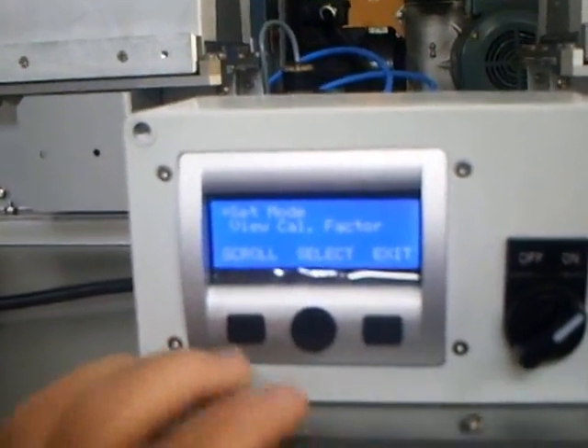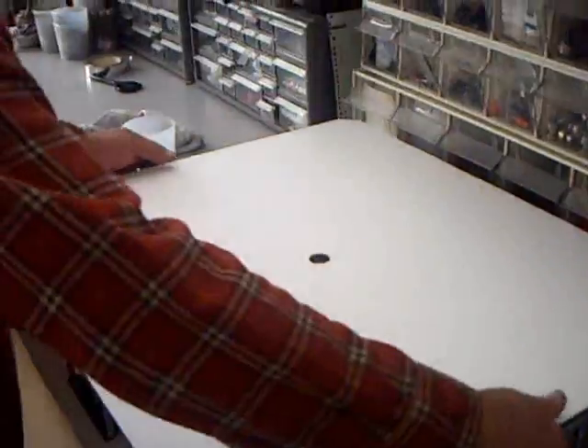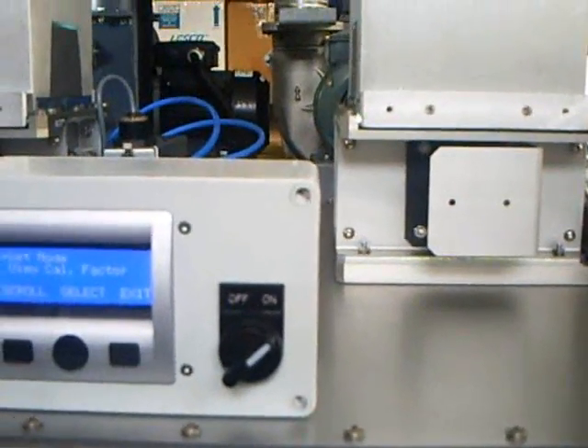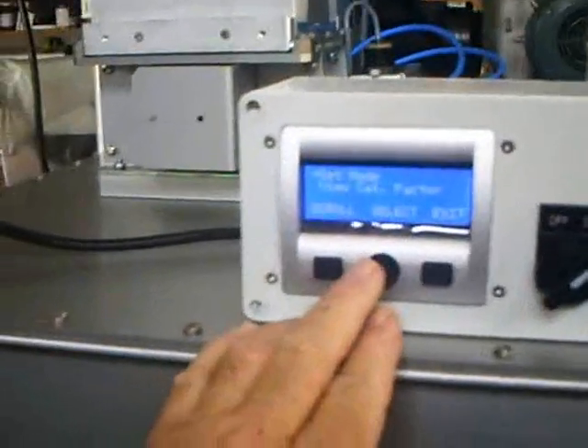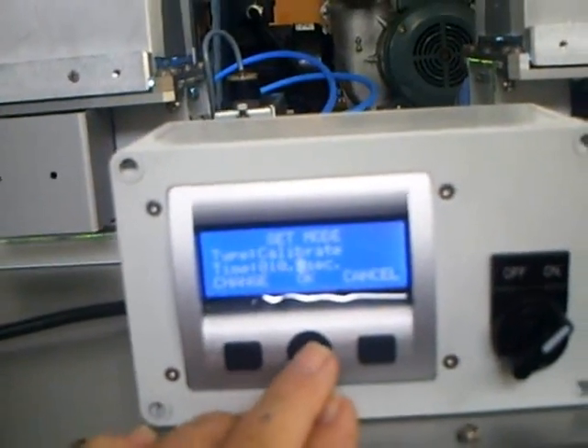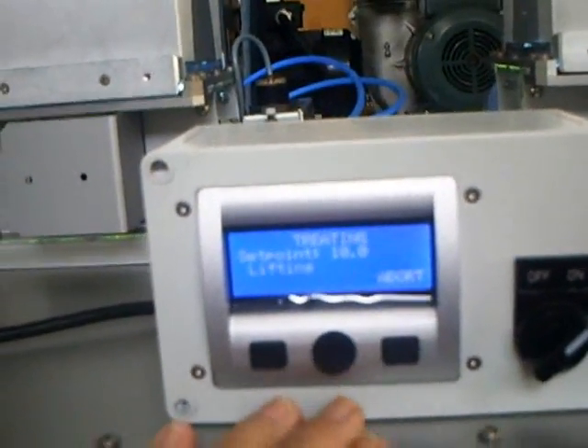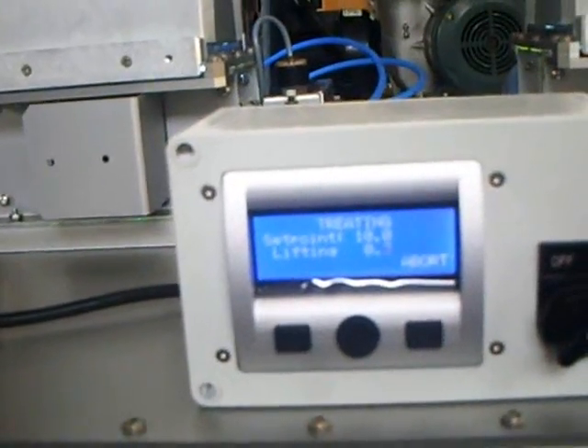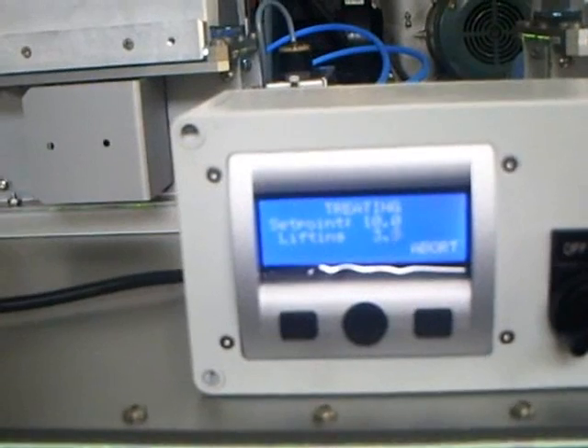So what we'll do now is we've reset the radiometer. We're going to install the cake pan fixture with the radiometer running in it, and what we're going to do now is close it up. The lamps are on the start mode, and we're ready. Now we're going to select go, calibrate, okay, exit, start. Now it's lifting, and you can see we're going through the 10-second calibration.